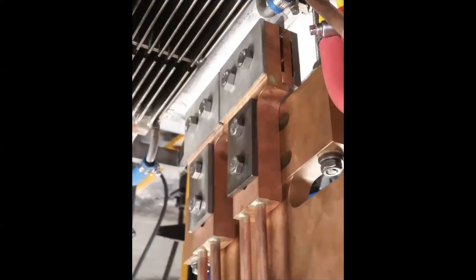Owens Corning is a top 500 company that manufactures fiberglass and fiberglass products. In their manufacturing plants, they use a bus bar to power a heating element that melts the glass. The last joint on their heating element is the terminal clamp we were tasked with improving. There are four clamps on each heating element that need to distribute 3,000 amps evenly or else the element fails.